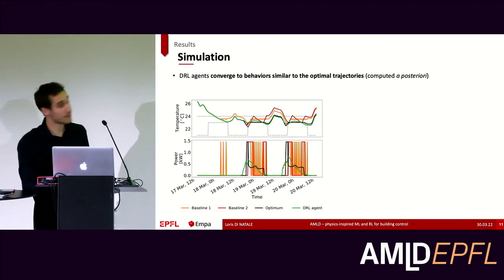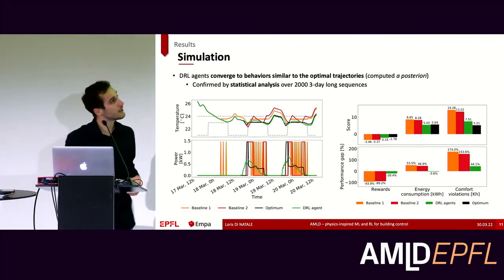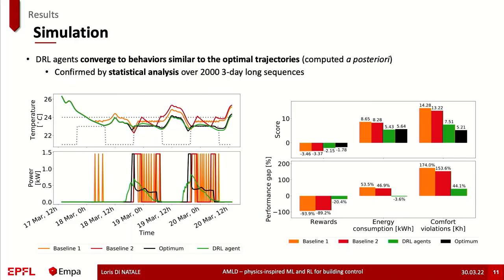Running this analysis for thousands of sequences, you can see the agent is always close to optimal and always crushing the baselines. We got energy improvements of 30% to 40% compared to the baselines, and much fewer comfort violations. It's really impressive that reinforcement learning is able to reach near-optimal solutions without any predictive power.